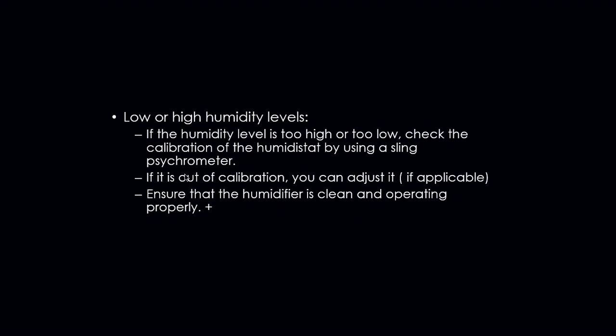Low or high humidity levels. Okay, if the humidity level is too high or too low, check the calibration of the humidistat by using a psychrometer. Compare what you're reading on your psychrometer to what the humidistat is reading. If they are not the same, then obviously we know that the humidistat is not calibrated properly, and therefore you're going to have issues with humidity levels. Okay, if it is out of calibration, some of them you can adjust. Some of them you're just going to have to replace. Okay, and ensure that the humidifier is clean and operating properly.